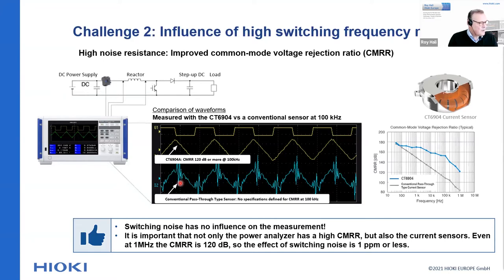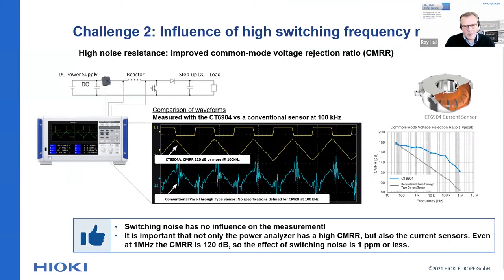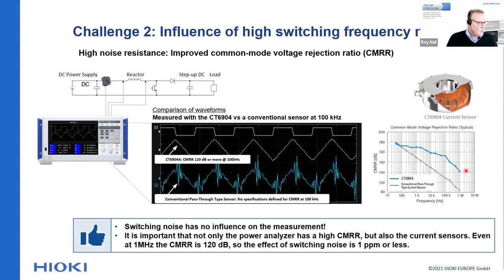This is not a good solution for accurate power measurement. However, there is a solution: the yellow trace E1 is measured with the CT6904A current sensor, which has a common mode rejection ratio (CMRR) of 120 dB or more at a frequency of 1 MHz. The 120 dB CMRR is equivalent to 1 ppm or less interference of noise at 1 MHz — in other words, you can simply neglect the influence of noise at higher frequencies. This example shows that it's not sufficient to have only a power analyzer with a high CMRR; your current sensor also needs an excellent common mode rejection ratio.